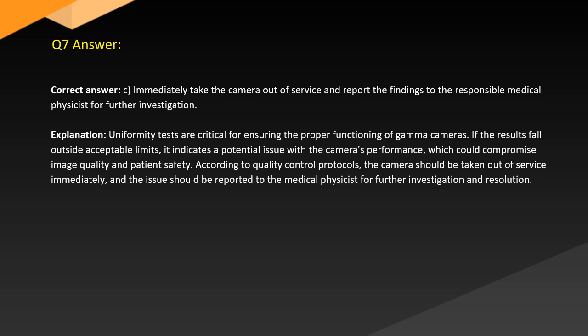Answer. Correct answer: C. Immediately take the camera out of service and report the findings to the responsible medical physicist for further investigation. Explanation. Uniformity tests are critical for ensuring the proper functioning of gamma cameras. If the results fall outside acceptable limits, it indicates a potential issue with the camera's performance, which could compromise image quality and patient safety. According to quality control protocols, the camera should be taken out of service immediately, and the issue should be reported to the medical physicist for further investigation and resolution.